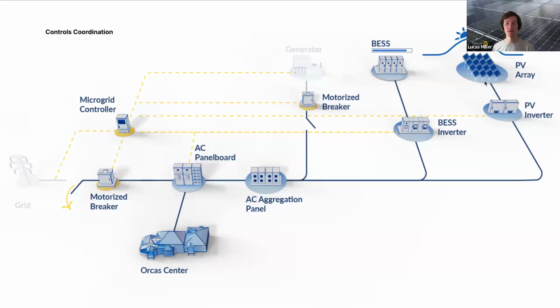And now we're islanded. So BESS and PV are our primary power sources on site. This BESS inverter is grid forming. So that will serve as our primary power source while we have sufficient PV to supply loads, as well as BESS power to supply loads at the Orcas Center. But let's say we get further in the day, now we're toward the evening, our PV array is really winding down, our BESS is starting to drain to a low state of charge. Here's where the controls really get complicated, in that we need to be talking with the generator in real time, looking at the BESS state of charge, measuring facility loads, and then determining who is grid forming at that time.